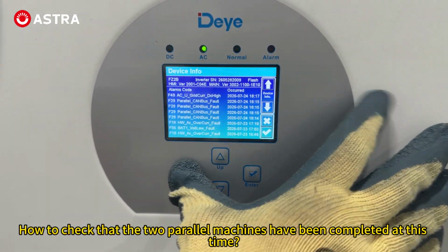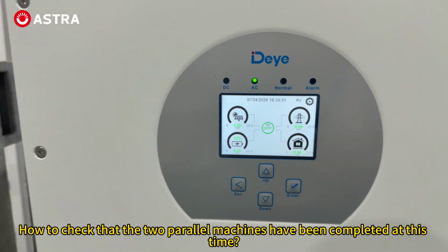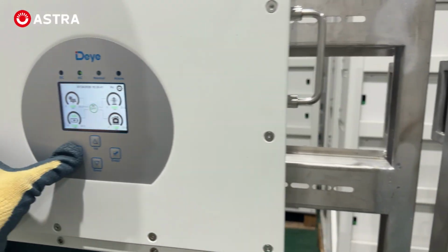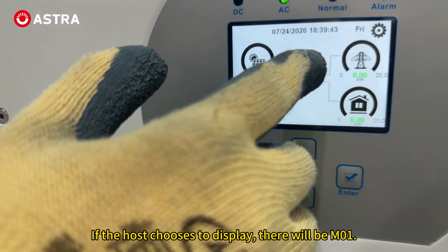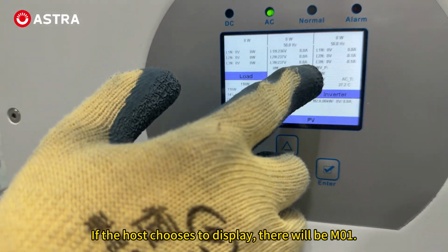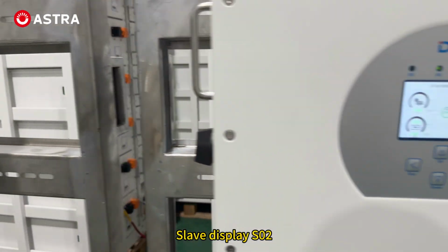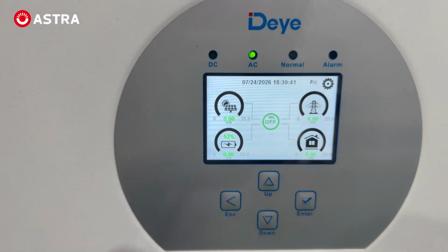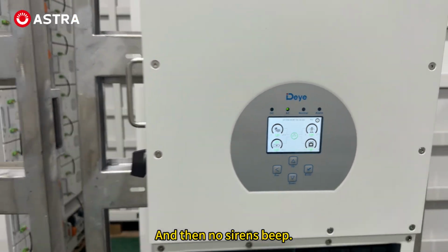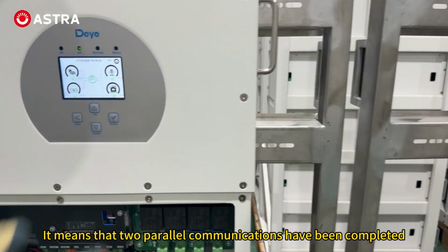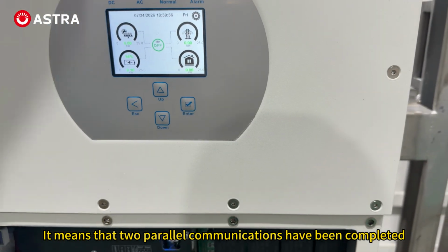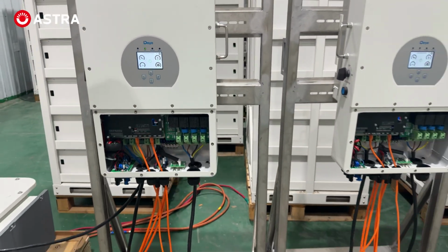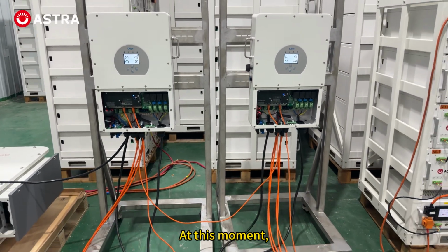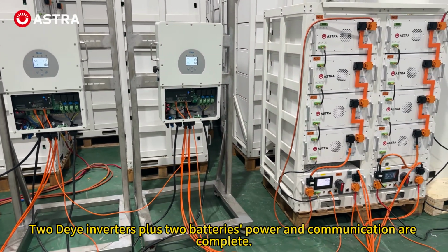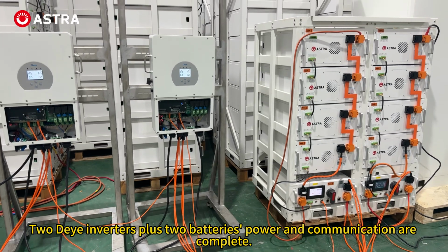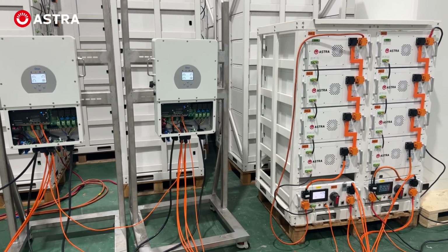How to check that the two parallel machines have been completed at this time? The host will display M01. The slave displays S02. And then no siren beeps. It means that the parallel communication has been completed. At this moment, the 2 inverters plus 2 batteries, power and communication, are complete.